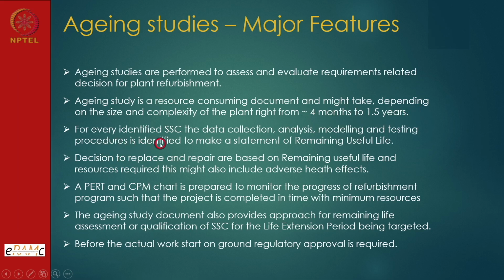For every identified SSC, data collection and analysis has to be done, and remaining useful life has to be determined. We should have an idea of this key factor, remaining useful life, either through quality metrics or through testing. For electrical and power cables, remaining life can be analyzed by taking a sample. For concrete, again take a sample and see how much deterioration has taken place compared to the fresh concrete that was used, where documents were available. The decision to replace or repair is based on remaining useful life.